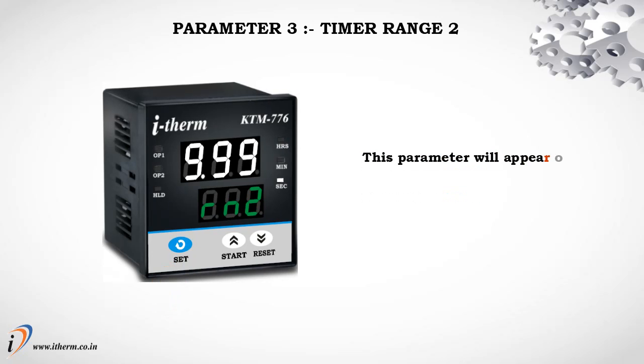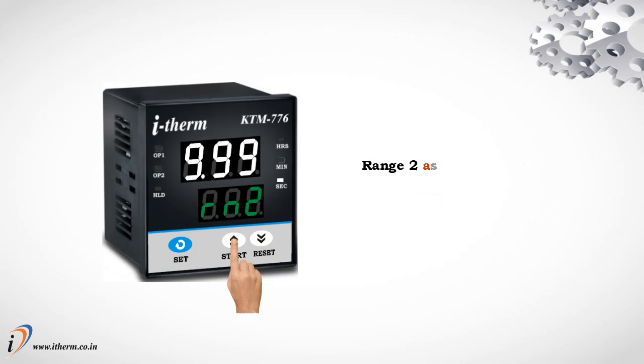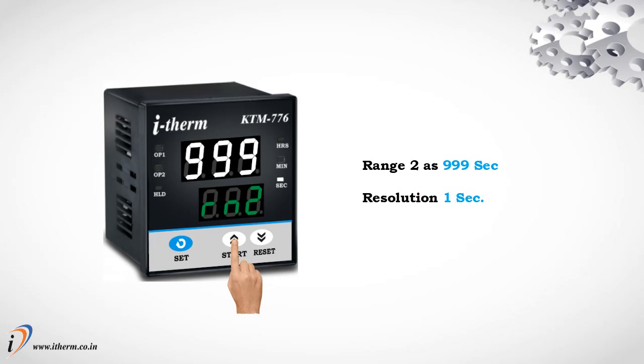Parameter 3: Timer Range 2. This parameter will appear only if the selected timer function is Cycle 1, Cycle 2, or Cycle 3. It sets the timing range and resolution for parameter Set Time 2. Range options: 9.99 seconds with resolution 0.01 seconds; 99.9 seconds with resolution 0.1 seconds; 999 seconds with resolution 1 second.